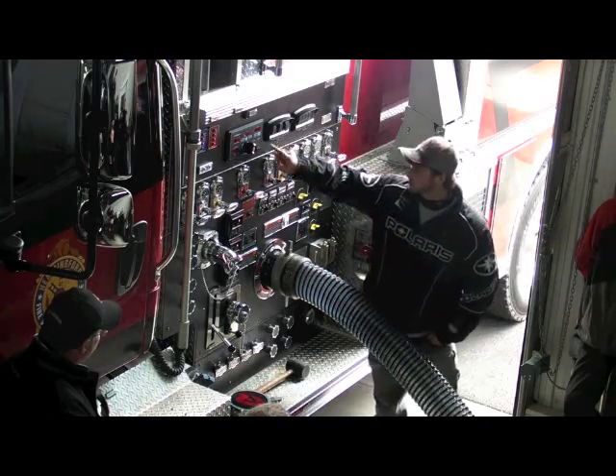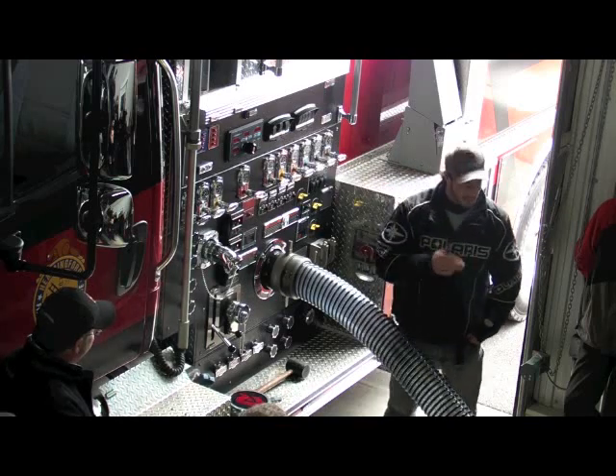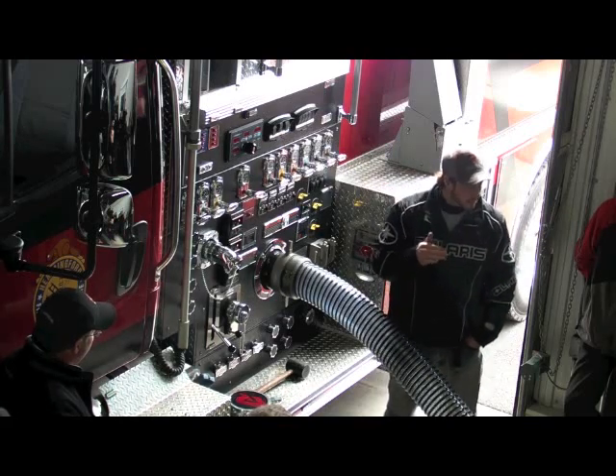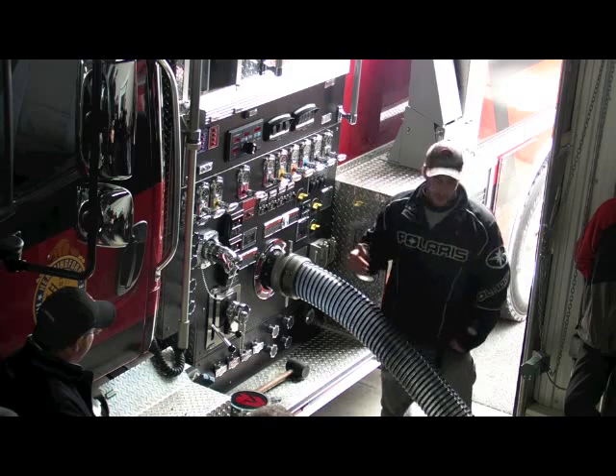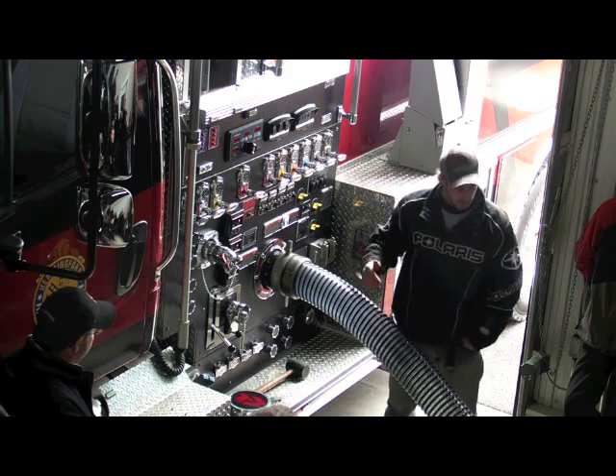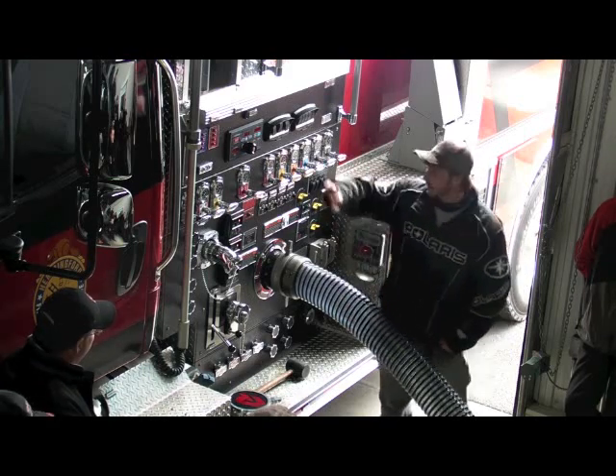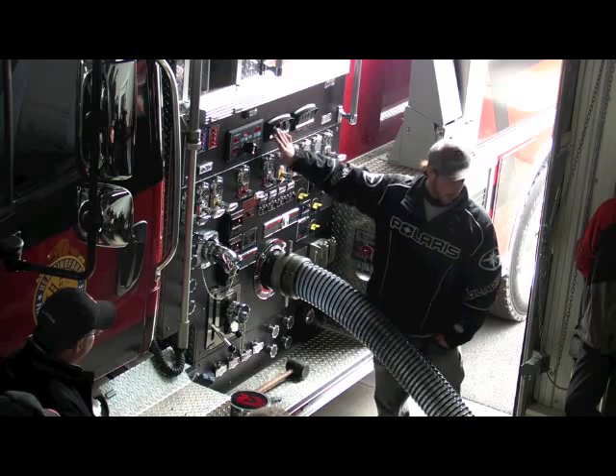The high pressure foam system that we see here is a fixed mix system, okay? So it will give you 1%, not more. Why do we do that? Because there's no use to go at more than 1% on the high pressure side, okay? So it's preset, I cannot adjust it - it's either on or it's either off.